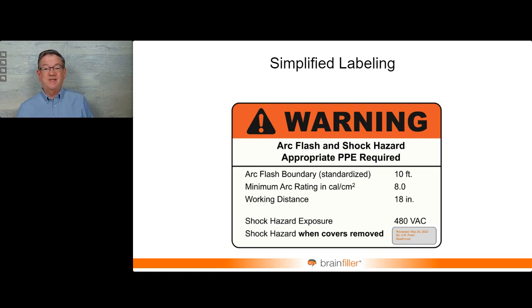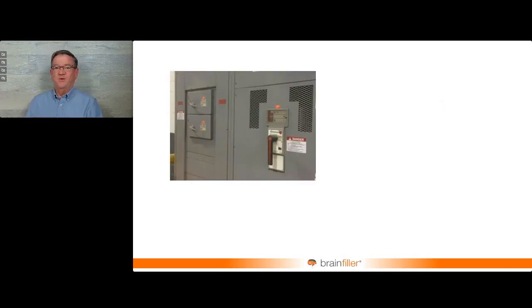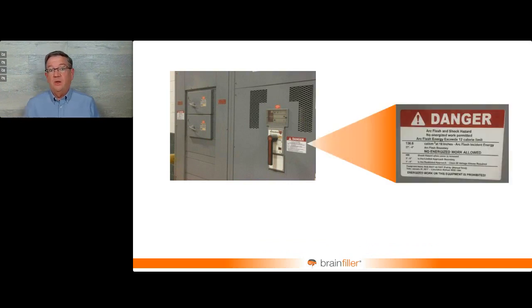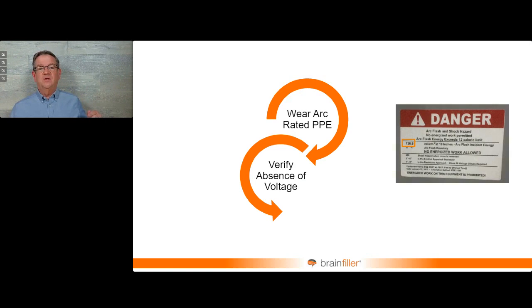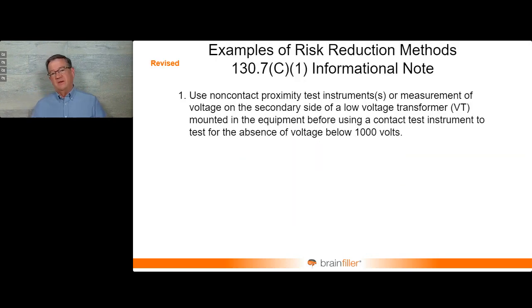So I'm surprised at how this is really starting to take off in the industry, and I developed it quite a few years ago. I actually had an article in Electrical Contractor magazine about it quite a few years ago as well. There's another issue: if you have a case where you have a really large calculated incident energy, like over 136 calories here, it's extremely dangerous. So, okay, well, we better de-energize that, make it electrically safe. Great. But I have to go test absence of voltage. And if it's still energized, which has happened in a few cases, that's not going to end well. So NFPA 70E introduced some methods to reduce the risk, kind of a preliminary check.